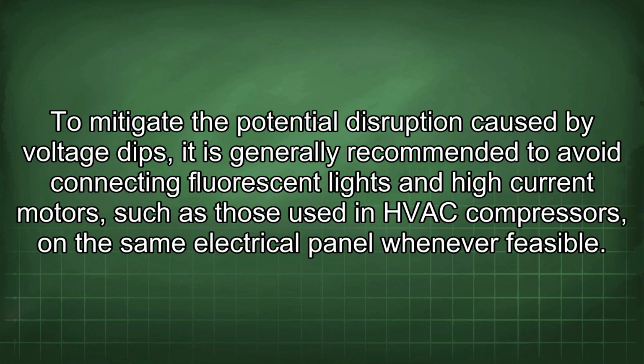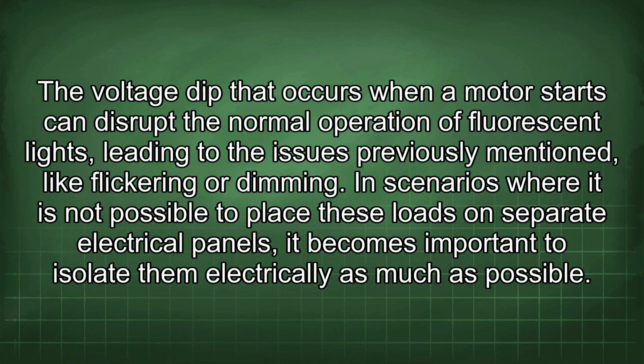To mitigate the potential disruption caused by voltage dips, it is generally recommended to avoid connecting fluorescent lights and high-current motors, such as those used in HVAC compressors, on the same electrical panel whenever feasible. The voltage dip that occurs when a motor starts can disrupt the normal operation of fluorescent lights, leading to the issues previously mentioned, like flickering or dimming.